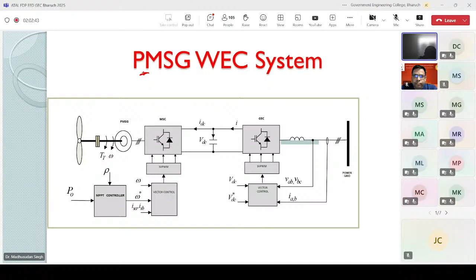So this grid side converter senses the DC current and also through its controller tries to maintain the DC link voltage. And at the same time, if there is any fluctuation in wind speed, the DC link is still maintained and the power quality is ensured. So this is a broad block diagram of a normal PMSG control.